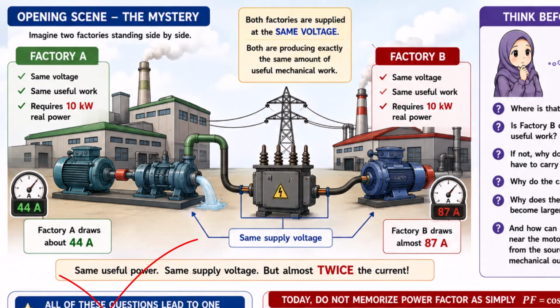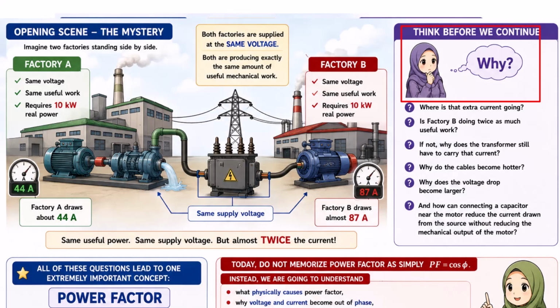Why? Where is that extra current going? Is factory B doing twice as much useful work? If not, why does the transformer still have to carry that current? Why do the cables become hotter? Why does the voltage drop become larger? And how can connecting a capacitor near the motor reduce the current drawn from the source without reducing the mechanical output of the motor? All of these questions lead to one extremely important concept called power factor.